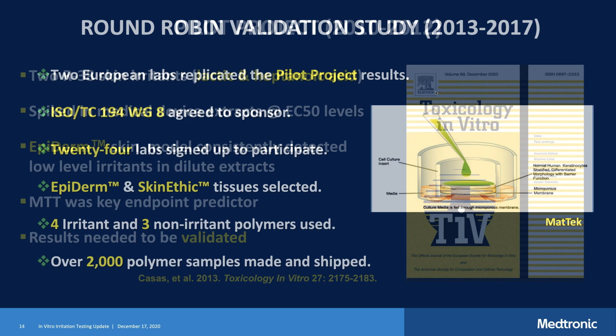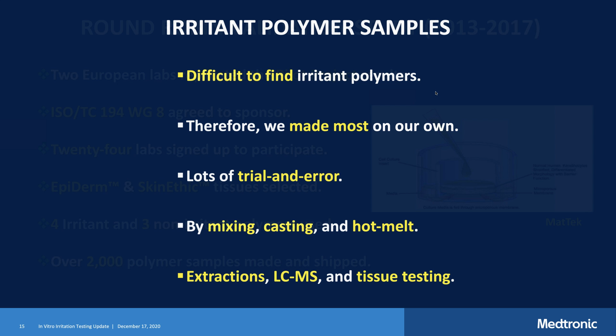It was pretty simple. We picked 2 skin irritants. We had 11 medical device polymers, and we spiked very low levels. And by spike, I mean we just titrated very low levels of lactic acid and heptanoic acid into polar and non-polar extracts of those 11 medical device polymers. And we tested 100 microliter doses onto EpiDerm skin models. EpiDerm is produced by MatTek in Massachusetts and in Slovakia. And our exposure time was 24 hours, and we used MTT, and we also used IL-1 alpha, looking for cytokines, but MTT is the key predictor. And we were able to show without a doubt that these EpiDerm tissues could identify low levels of these irritant chemicals in medical device extracts.